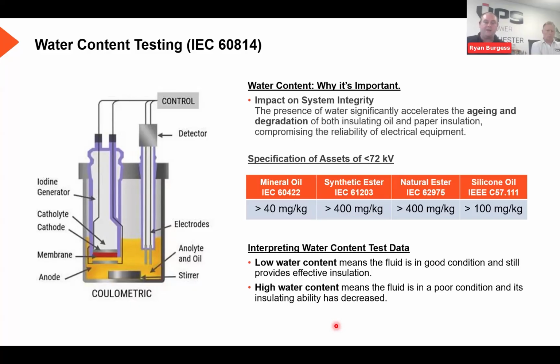So why does each fluid type, as you can see, have a different specification? It's all to do with the polarity of each fluid. So a mineral oil has the lowest polarity, meaning it can absorb the least amount of water before becoming saturated and ultimately reducing its insulating properties. Whereas if you look at something like a synthetic ester, that's at the complete opposite end. That has a significantly higher polarity, and due to that, it's able to absorb larger amounts of water before those properties are degraded. So when it comes to looking at the results, no matter the fluid type, a low water content is good and indicates that the fluid itself is still effective, whereas a high water content is showing that the fluid is poor and starting to degrade, and those properties are reduced.